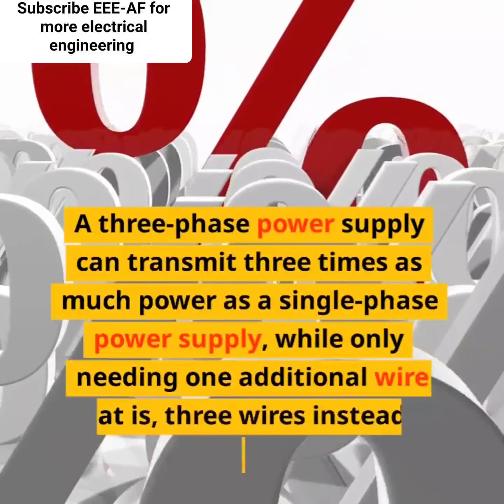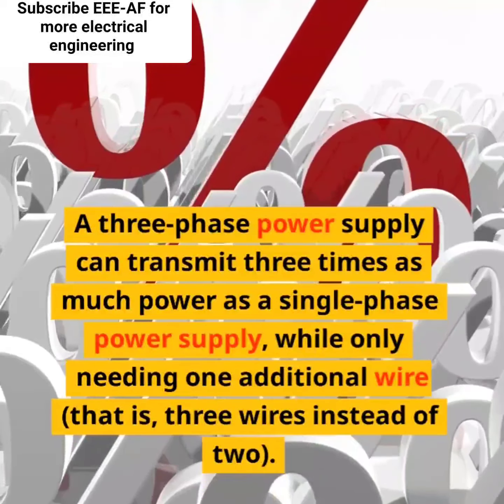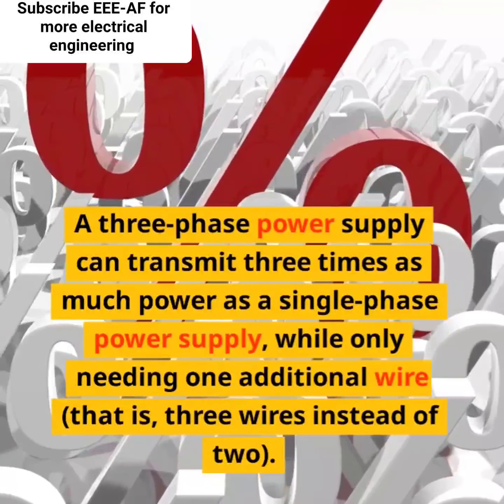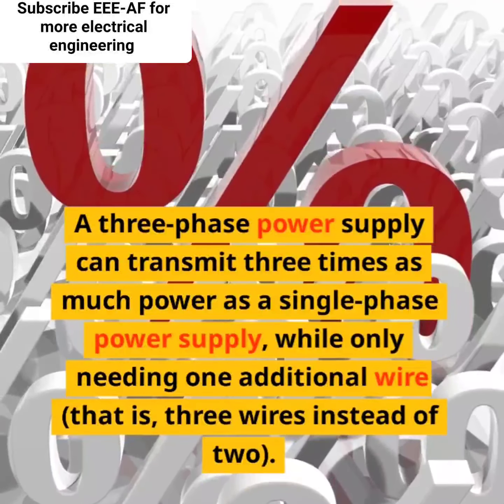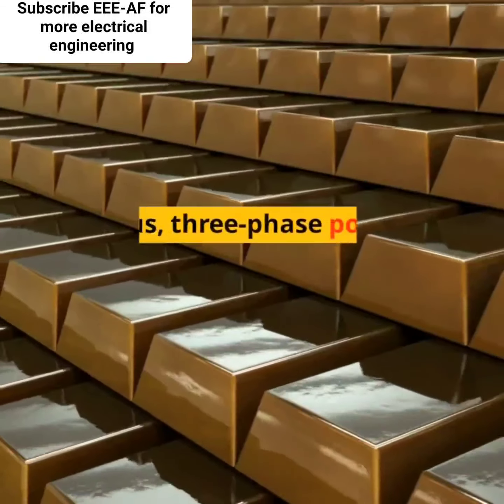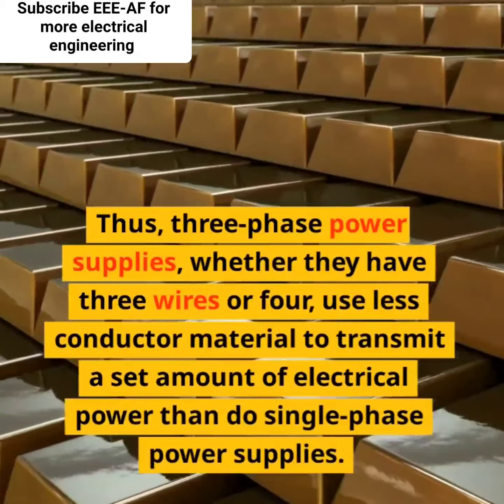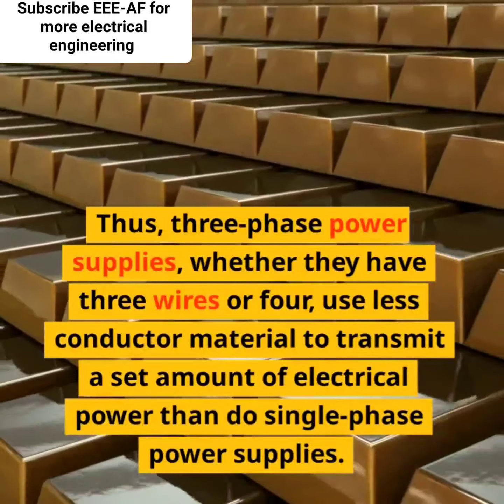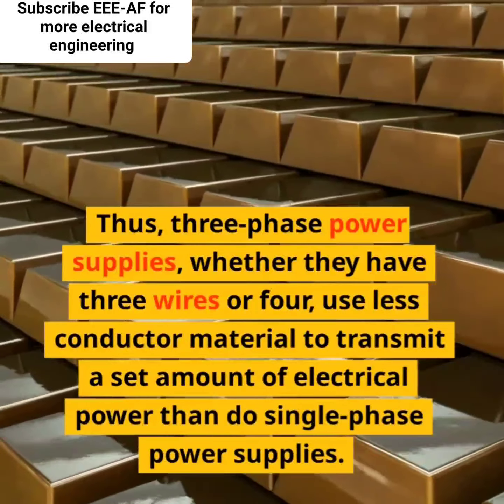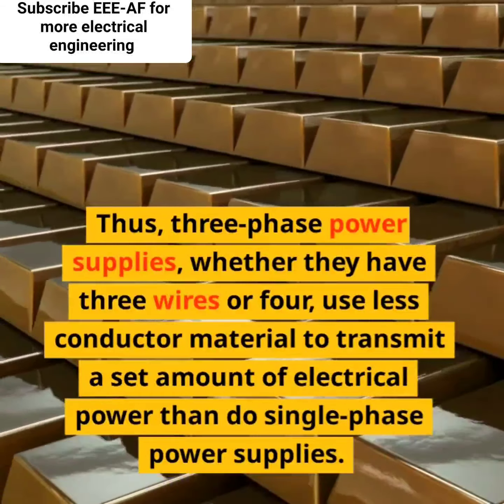A three-phase power supply can transmit 3 times as much power as a single-phase power supply, while only needing one additional wire, that is, 3 wires instead of 2. Thus, three-phase power supplies, whether they have 3 wires or 4, use less conductor material to transmit a set amount of electrical power than do single-phase power supplies.